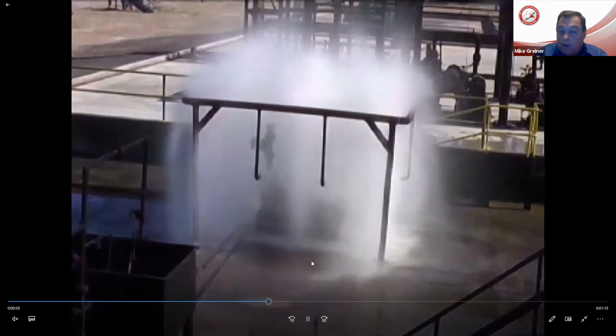So their insurance company was familiar with the encapsulator agent's three-dimensional Class B fire capabilities. And so on that project, there's 3 separate phases. We've completed phase 1, which is engine rooms 5 and 6. And I think it resulted in an 1,800 gallon F500 bladder tank. It will proportion into 6 different risers and feed into these nozzles. We call these nozzles VEEP nozzles, vapor encapsulation explosion prevention, or sometimes we refer to them as rotating nozzles.